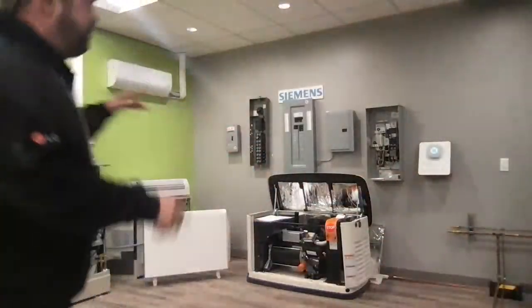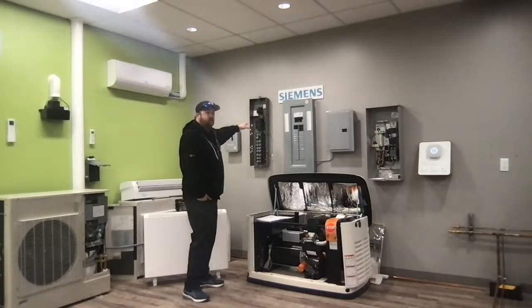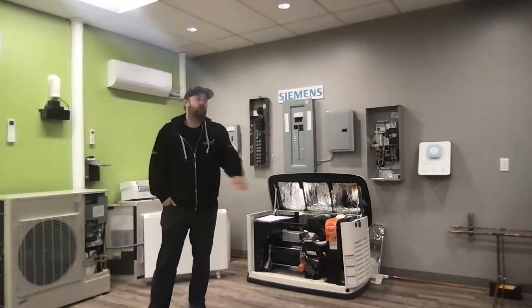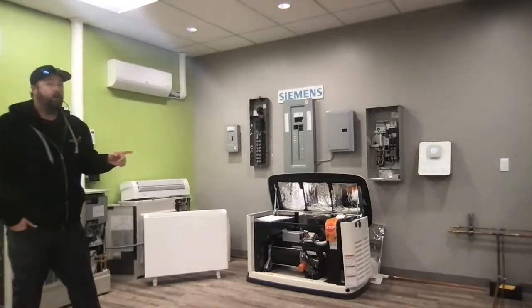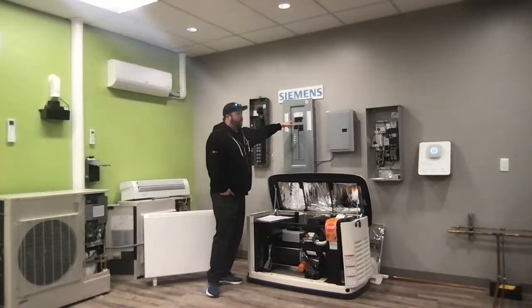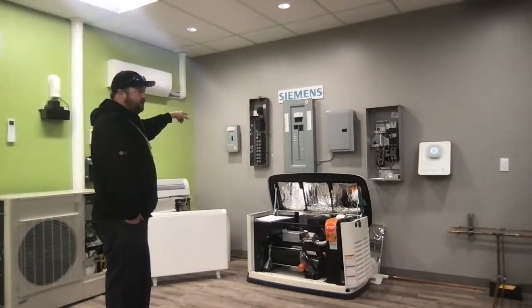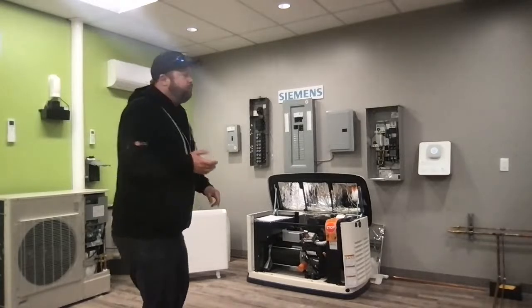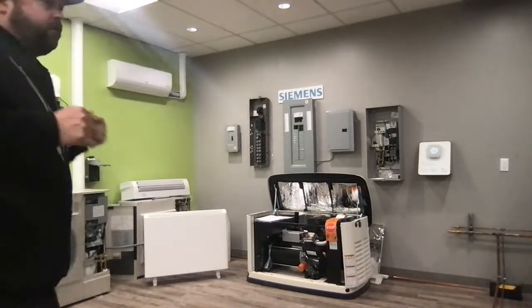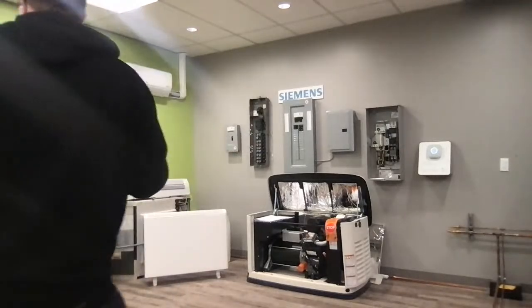Back to power — on 100 amps, if you're keeping oil and don't have a hot tub or heated swimming pool, chances are you can fit all the heat pumps you need right now with no upgrade necessary. If you're looking to get rid of oil on 100 amps, you're going to 200 amps — because we're replacing that oil primary heat with some sort of electric heat: electric boiler, electric baseboards, or electric furnace.